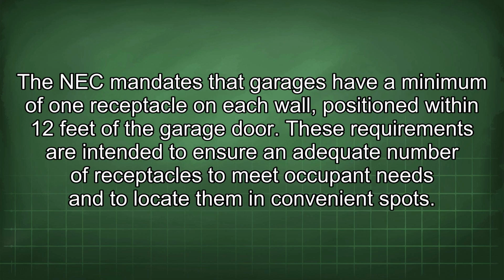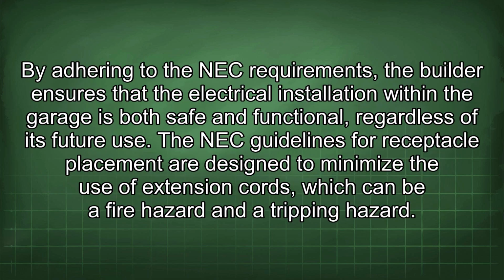The NEC mandates that garages have a minimum of one receptacle on each wall, positioned within 12 feet of the garage door. These requirements are intended to ensure an adequate number of receptacles to meet occupant needs and to locate them in convenient spots. By adhering to the NEC requirements, the builder ensures that the electrical installation within the garage is both safe and functional, regardless of its future use. The NEC guidelines for receptacle placement are designed to minimize the use of extension cords, which can be a fire hazard and a tripping hazard.